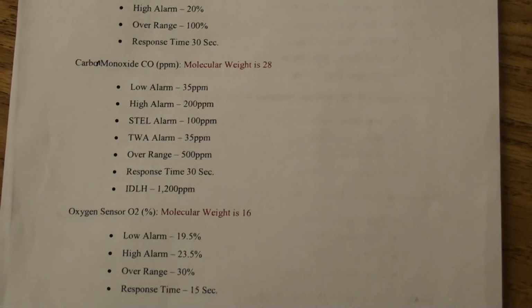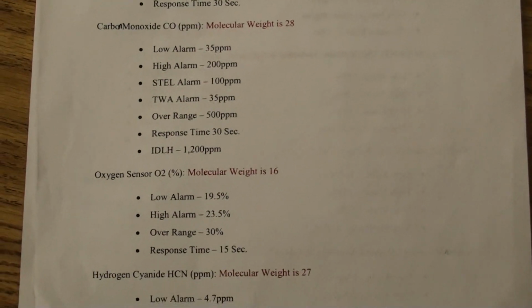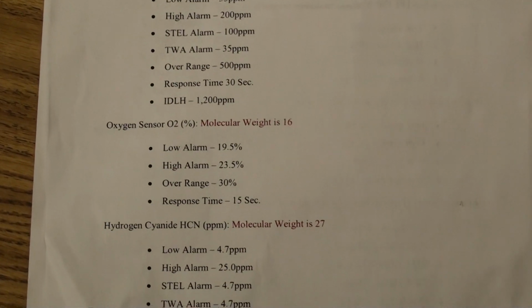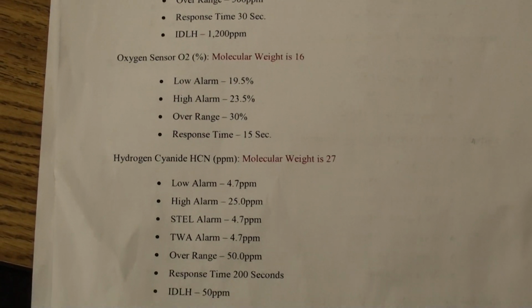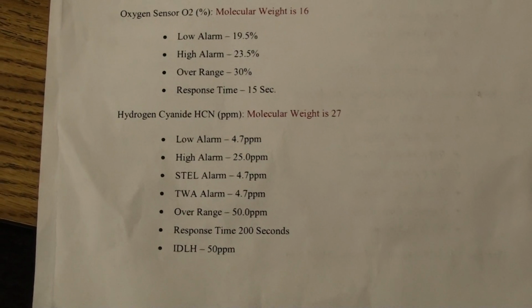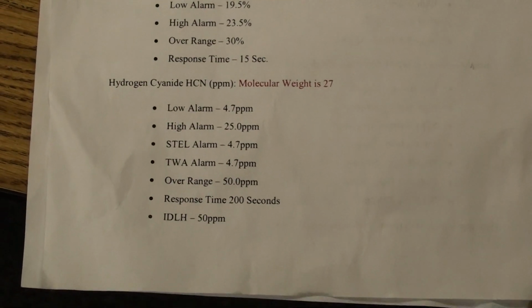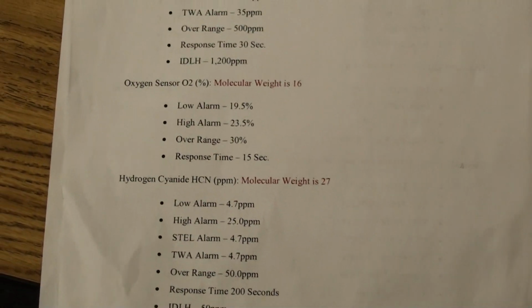And the only way to get a new sensor is to take it to 5, and the techs out there, the hazmat techs, can replace the sensors. I believe they're around $350. So these aren't to be put in front of an exhaust or anything to try to get a reading, because you'll hit that over range real fast.